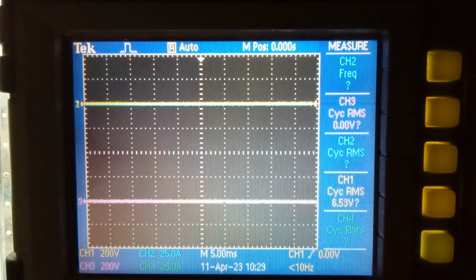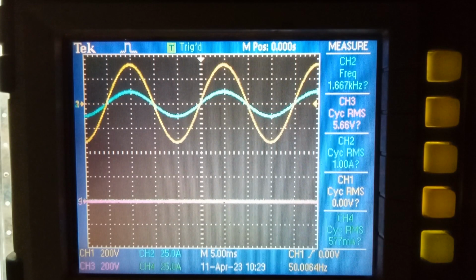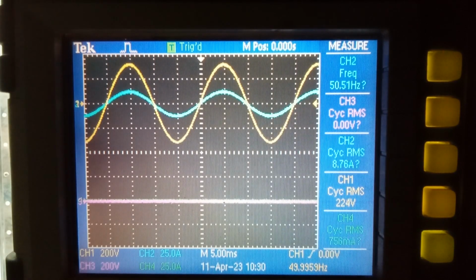Okay, now we're going to turn the inverter on. So we have in yellow the inverter 230 volt 50 Hertz waveform, and in blue the inverter current. That's powering a 2 kilowatt load at the moment. Now we're going to start the generator. You'll see a flat top waveform out of the generator moving across the screen. It'll come into sync with the generator and then they'll connect.